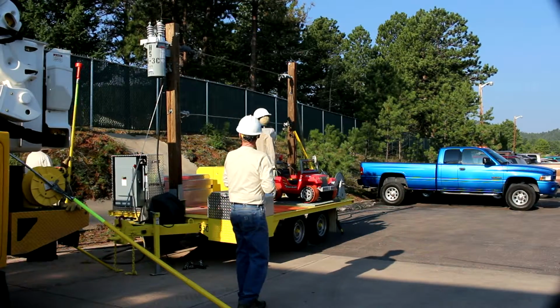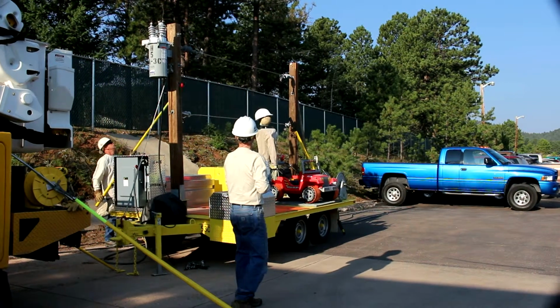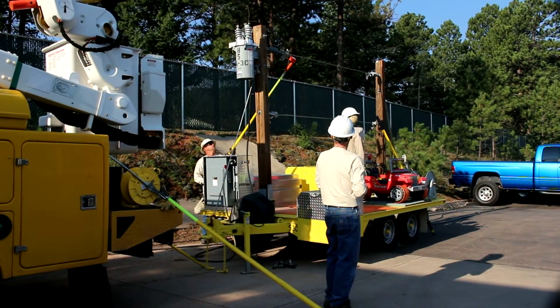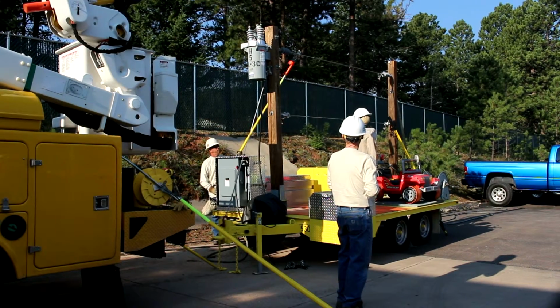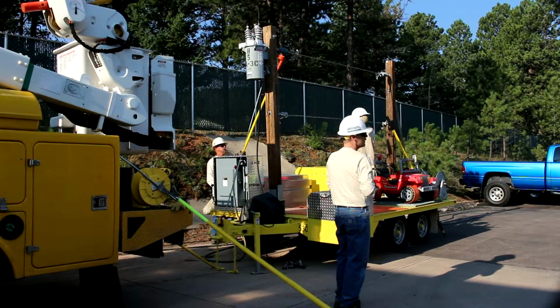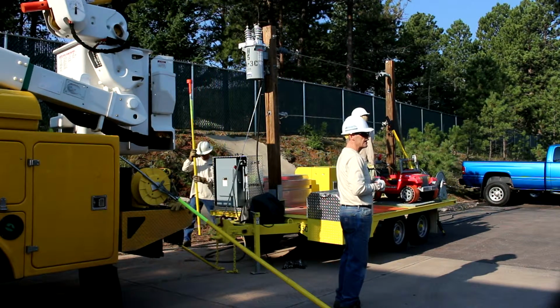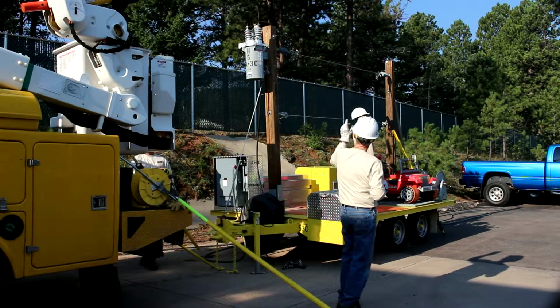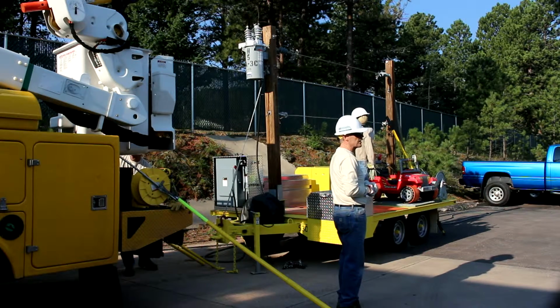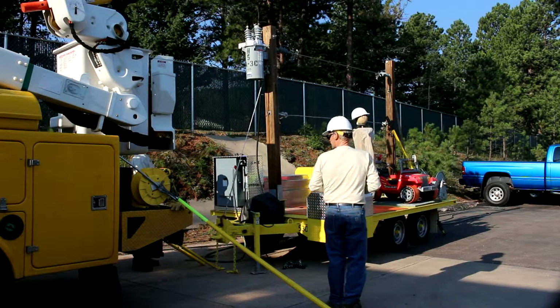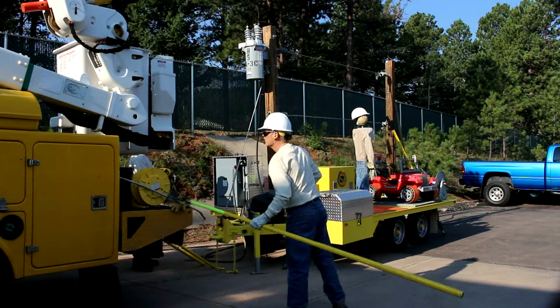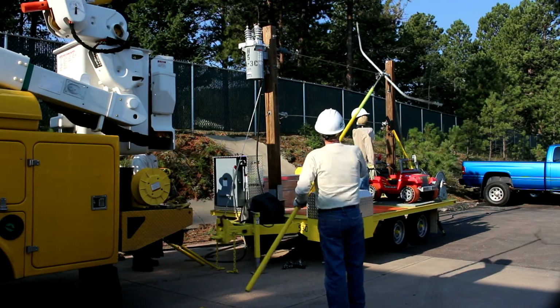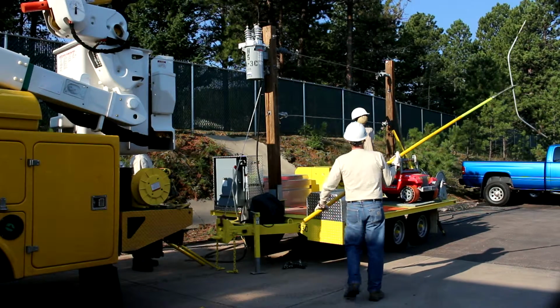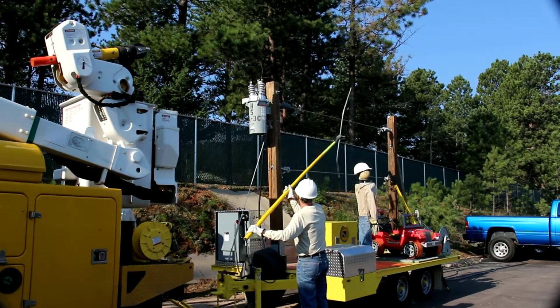So we're going to test to make sure we're hot here - we have an indicator that will tell us if the line's hot or not. Repeat signal means the line's energized. So we know our line is hot, anything up on that is now energized at 7,000 volts. We notice it's not jumping anywhere. Our little stick here, we're going to bridge across here just to show you that line is hot.